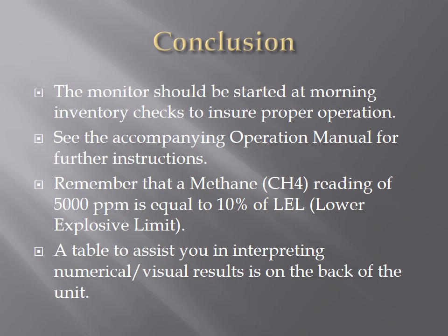Very important, remember that methane, or CH4, at a reading of 5,000 parts per million is equal to 10% of the lower explosive limit. That should alert you that you're in a dangerous situation and you need to take appropriate actions. And when you do get an alarm, whether audio or visual, there is a table on the back of the unit itself that will assist you in interpreting what those results, those lights, and those beeps mean.